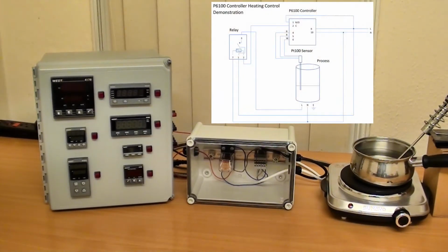The set point ramping feature is used to protect the process or equipment from damage if there were any sudden changes in the set point, resulting in a rapid rise in the process variable. Without the set point ramping feature, any changes in the set point would cause the process to drive to a new value at the fastest rate that it was capable of doing. With set point ramping, the set point is moved slowly towards its target value.